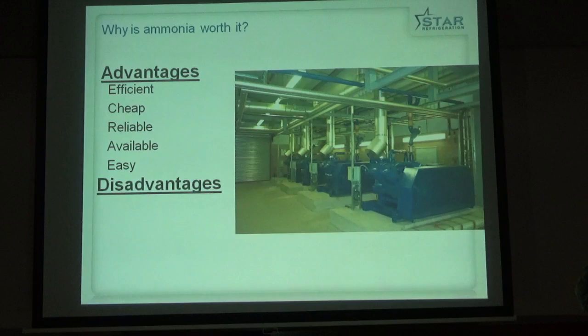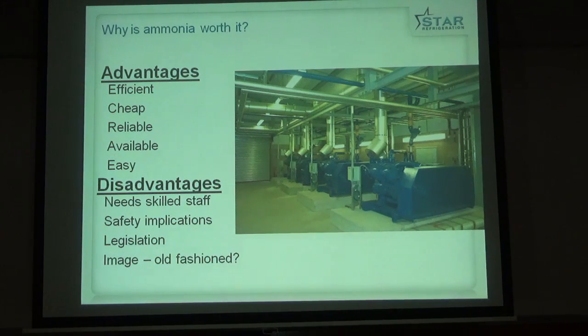It has some disadvantages. You need to have skilled staff to work with it because there are safety implications. It's both flammable and toxic. And provided you recognise these things and deal with them, that's okay. But if you don't, you'll be in trouble. There is a fairly significant amount of legislation surrounding its use. But then on the other hand, there is for all the HFCs now. Anybody who was paying attention to the meeting in Kigali, Rwanda, just a few weeks ago, would see that HFCs are actually now on the phase-out list, as well as CFCs and HCFCs. So the revolving door has turned a little bit further. And ammonia has this image that it's old-fashioned. You know, that's the way my grandfather did refrigeration.